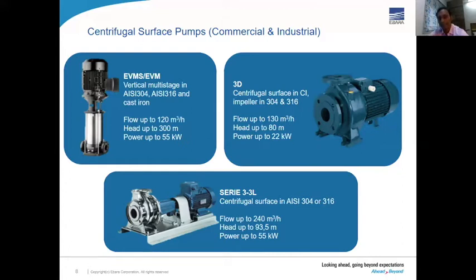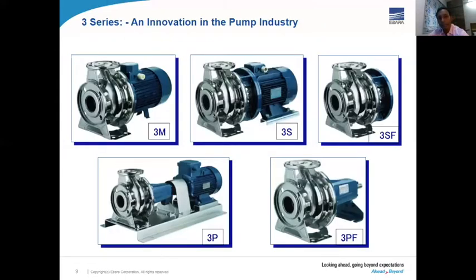That's the Series 3, which is a patented product again of Ebara, which is the casing. Basically, you can have it as a monoblock or a close coupled or a long coupled. This product, you can use it for the booster set. The main advantage is that it has a sheet metal impeller, so your torque on the motor is less. So you can use it for the booster application. If the pump is a cast pump, yes, they can have a higher torque on the motor shaft, so it may not be feasible when you have a high number of start stops. Whereas this, having a sheet metal, you can use it for the booster pumps as well. And it has a very high efficiency because of the volute of the casing, which we manufacture.